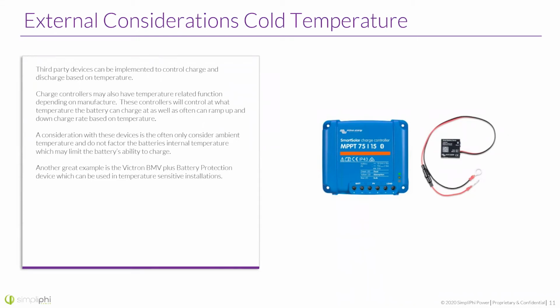It is important to consider most of these devices only consider ambient temperature. They do not factor in the battery's internal temperature, which may limit the battery's ability to charge, even when the temperature inside of the battery is not that low. So what I mean by that, if it's 10 degrees warmer in the battery, but the sensor is on the outside of the battery, it will stop charging before it's actually really needed to. So that is something to consider as well.